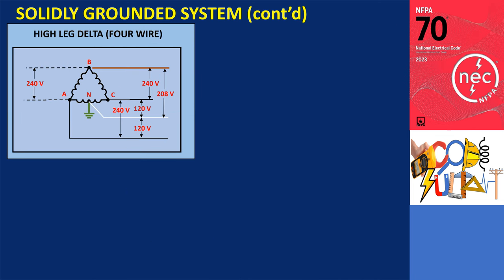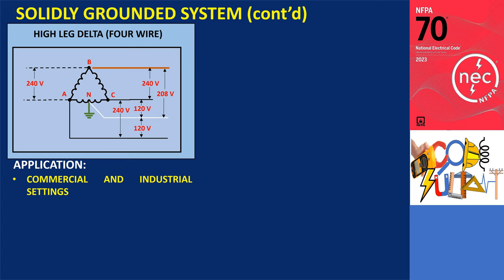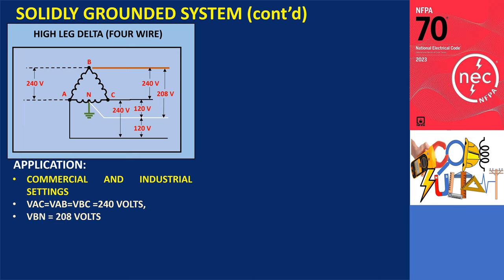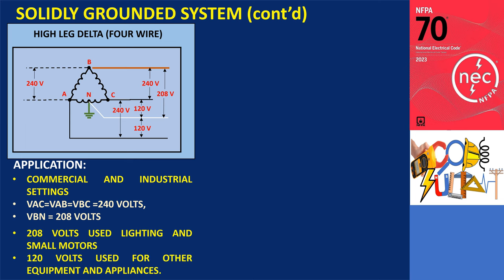Four-wire delta, also known as high leg delta, is a type of electrical distribution system commonly used in commercial and industrial settings. It is a three-phase system using a combination of a center-tap transformer and three-phase transformers. One phase winding is center-tapped to create a neutral connection, while the other two windings are connected in a delta configuration. The voltage between any two phases is typically 240 volts, while the high leg — also known as the wild leg or stinger leg — and the neutral is typically 208 volts.